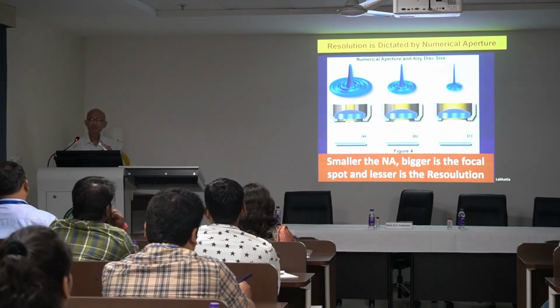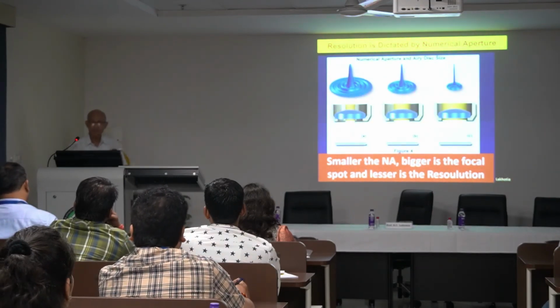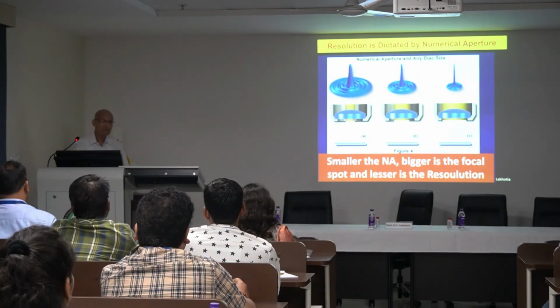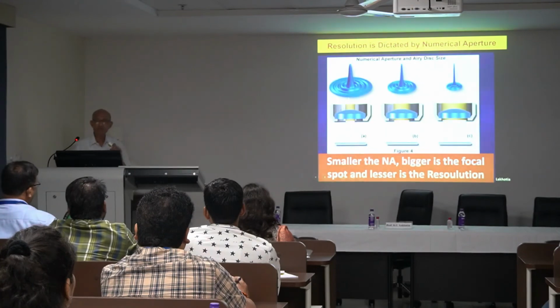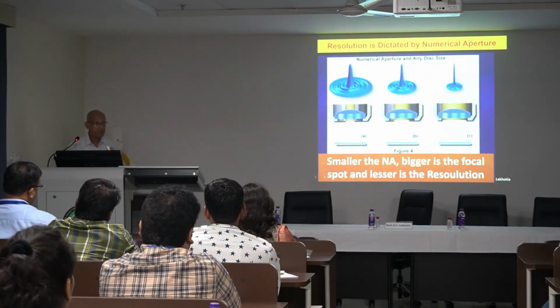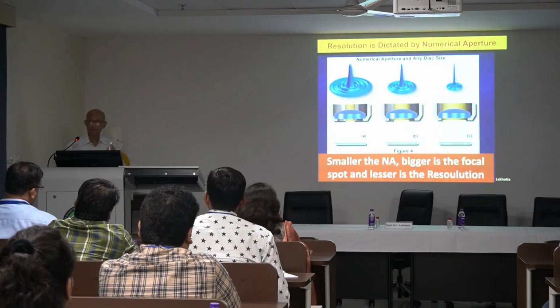Water immersion we use when we are trying to look at cells in culture or organs in water, so that the object can be dipped in water and can be used to focus. They don't get affected by water. But if you use any immersion objective without an immersion medium, you won't see anything. With a water immersion objective, you cannot use glycerol or oil, and vice versa.